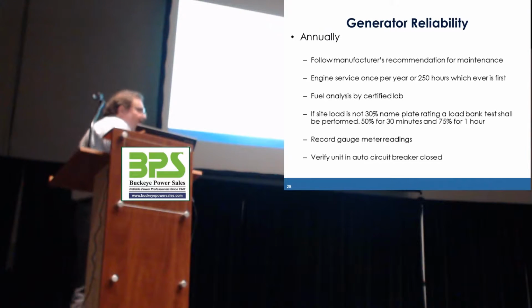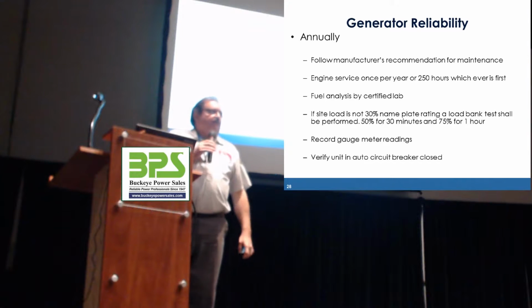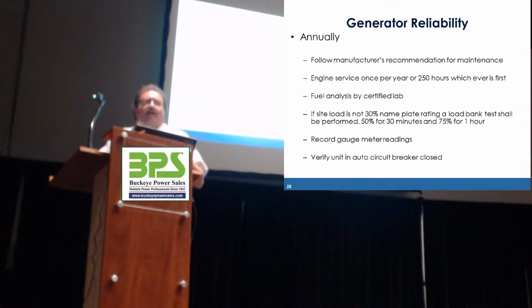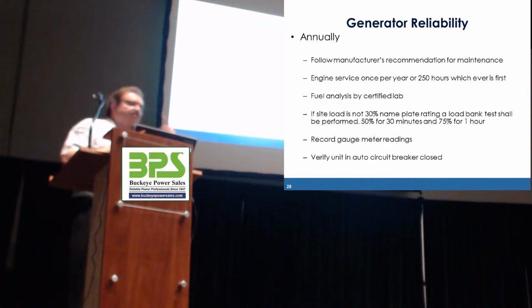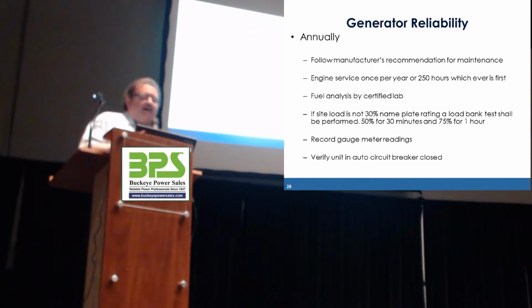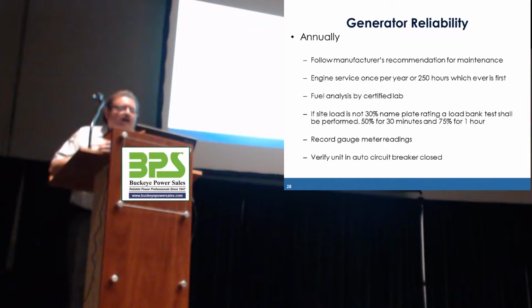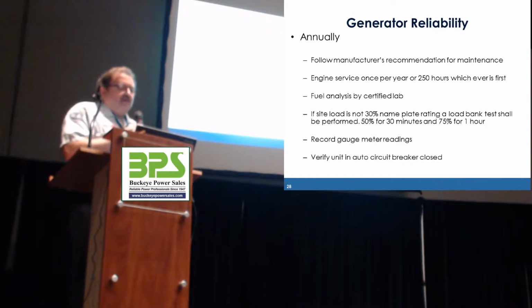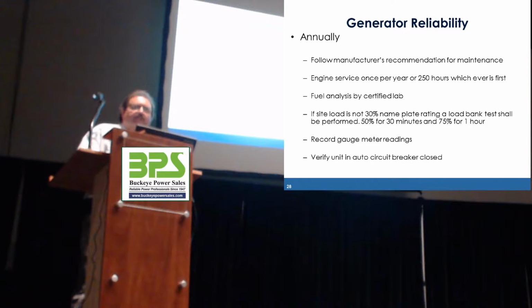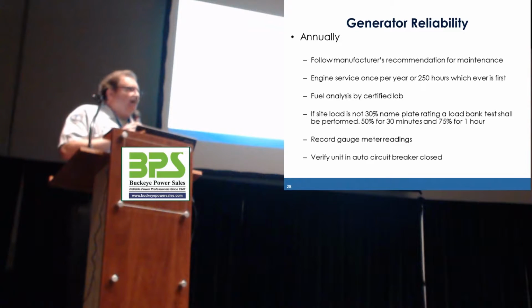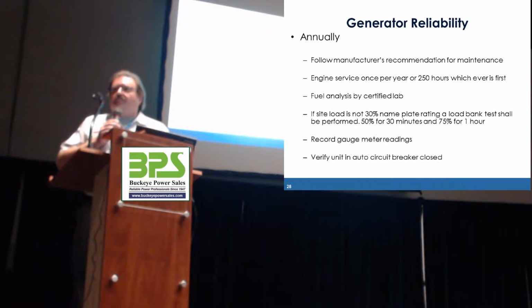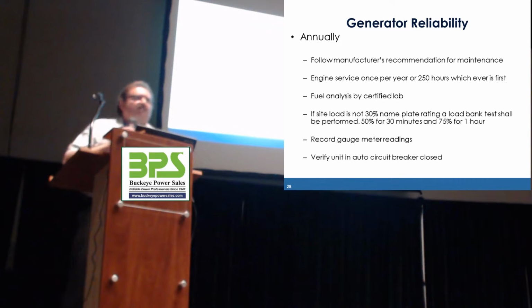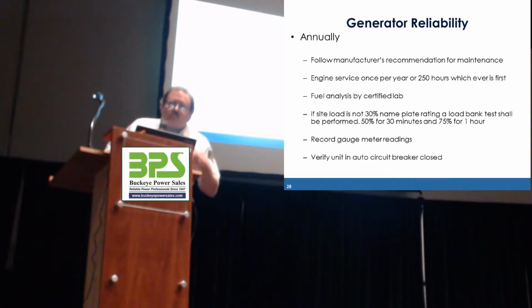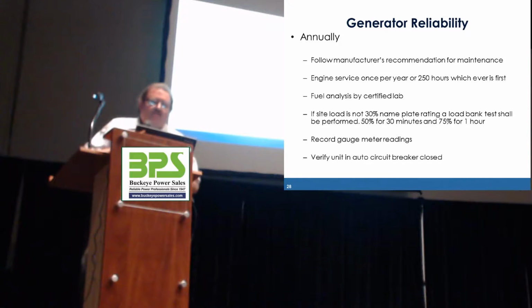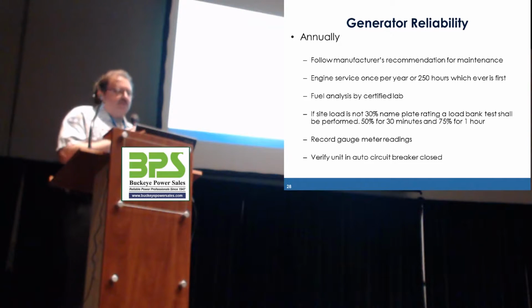Annually, it says that we have to follow the manufacturer's recommendation for maintenance. And it doesn't matter who the manufacturer of the equipment is, if it's CAT, if it's Kohler, whatever, they all have their manufacturer's recommendation for maintenance. As a general rule of thumb, it's once a year or every 250 operating hours, whichever comes first. And in almost every case, that once a year is going to come first, right? Some manufacturers will allow for sample testing, but either way, you have to follow that manufacturer's recommendation.